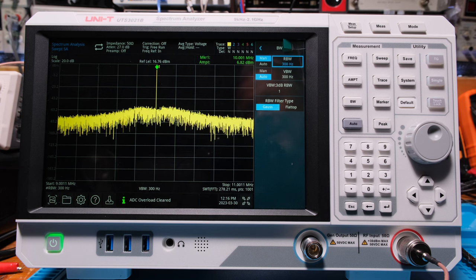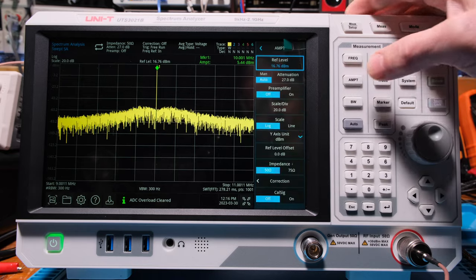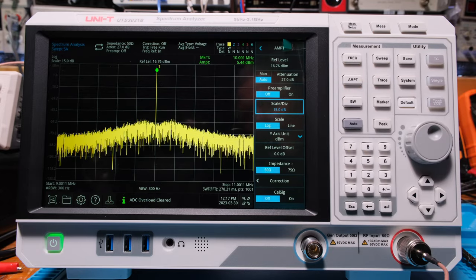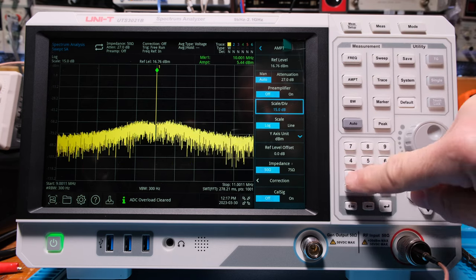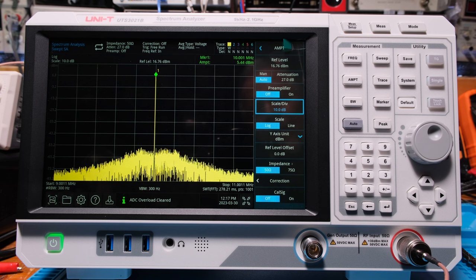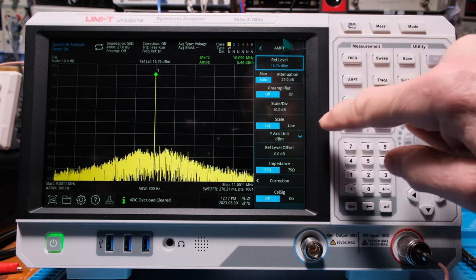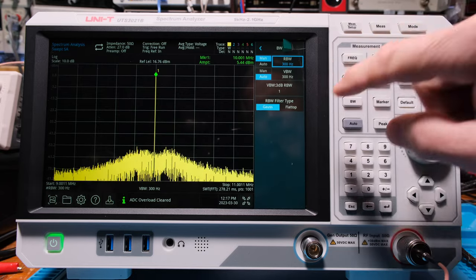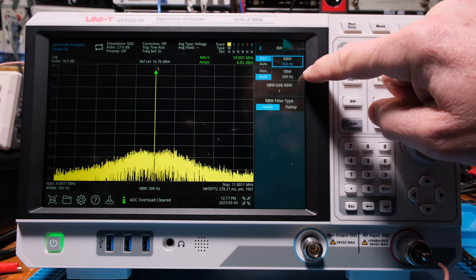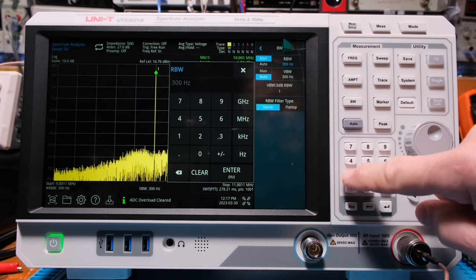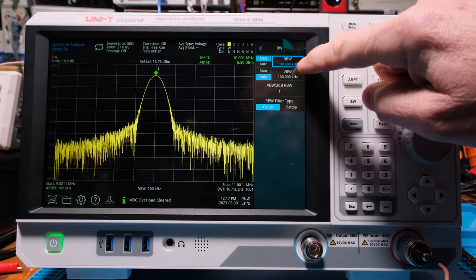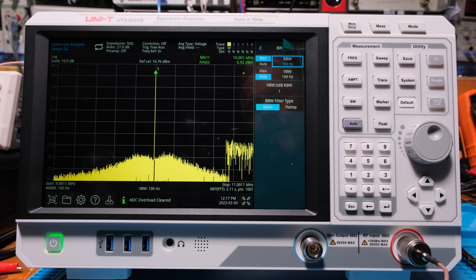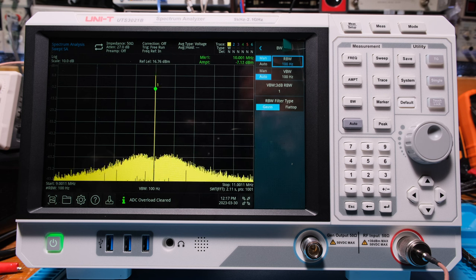Adjusting the amplitude scale to 15 or back to 10 dBs per division makes all the difference in how much information you're seeing. We also have this VBW — video bandwidth — filter. Let's set it to a lower value, about one-third. That knocks it down a bit and it's looking better. So that's the overall idea of how these settings work together.